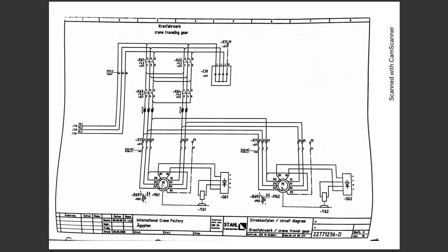But if I release my hand from the motor, the contactors will stop, so there will not be any power inside the motor, so those 2 wires will not have power actually. So this rectifier will stop supplying power to this braking. So this braking will make a clutch. It will close and will make this rotor stop instantaneously. So if this rectifier has power from inside the motor, it will make this brake to be released. If the power stops, it will make this brake close and make this motor stop instantaneously.